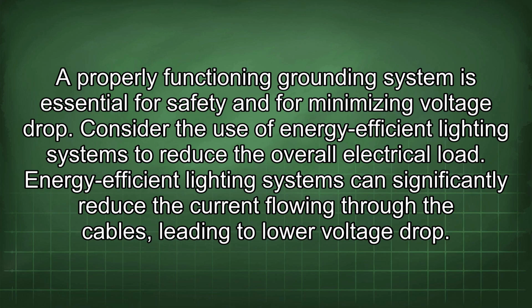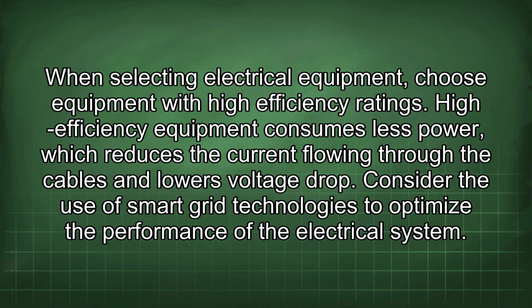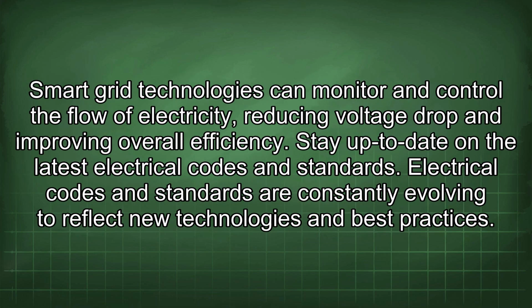Consider the use of energy-efficient lighting systems to reduce the overall electrical load. Energy-efficient lighting systems can significantly reduce the current flowing through the cables, leading to lower voltage drop. When selecting electrical equipment, choose equipment with high-efficiency ratings. High-efficiency equipment consumes less power, which reduces the current flowing through the cables and lowers voltage drop. Consider the use of smart grid technologies to optimize the performance of the electrical system. Smart grid technologies can monitor and control the flow of electricity, reducing voltage drop and improving overall efficiency.